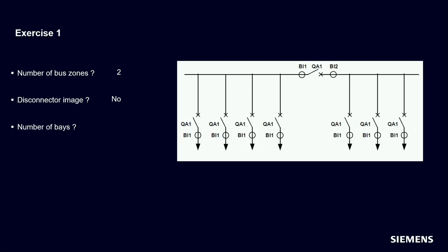How many bays do we need? Will be interesting. There are 8. Let's count. We see 4 feeders on the left side of the coupler, 3 feeders on the right side of the coupler, and for the complete coupler, even if it's a coupler with 2 CTs, we need only 1 bay. So all in all, we need 8 bays in this example. How many CTs do we need? Of course, it's 9. We have 8 bays, but for the coupler bay we need 2 CTs, so we need 1 CT more than bays, so all in all we need 9 CTs.